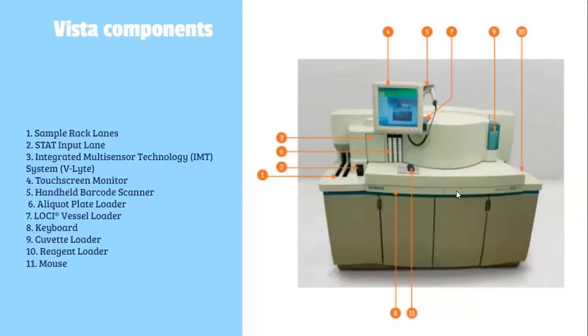So some of the Vista components, bring your attention to number 6, which is the Aliquot plate loader, along with number 9 and number 7. Number 7 is the loci vessel loader, and number 9 is the cuvette loader. Before we start QC, it's always important to make sure that we have everything loaded and supplies are refreshed, just to make sure that QC goes as smoothly as possible and there's no errors of low vessels or anything like that to put us behind.